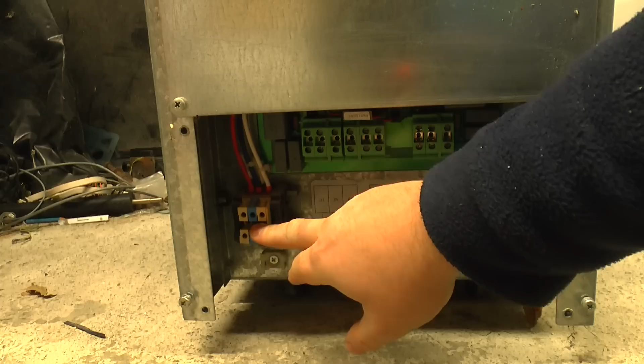And as I said, you can see on the back it's branded up as a Powerware rather than the 3000T. Now, obviously a UPS this size is meant to be hardwired. You can see you've got connections here for an external battery bank. It's normally got the batteries inside, I'll show you shortly. There's the terminals for the output, there's the input terminals, and this is the bypass connection as well, so you can run it on there.